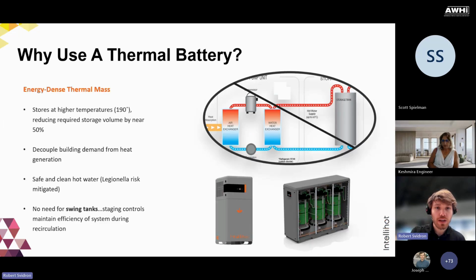Okay, and then I just wanted to talk quickly about why a thermal battery is the approach that we're taking. There's a few items here. First would be that having a thermal battery means you can actually store energy at much higher temperatures. So we're going to be storing much closer to 200 degrees, which reduces your required storage volume because you could pack more energy into that same amount of space. If you compare the thermal battery with a traditional hot water storage tank that's storing water at 140, we're about half the size with the same amount of energy. And so that helps to pack more equipment into a smaller space.